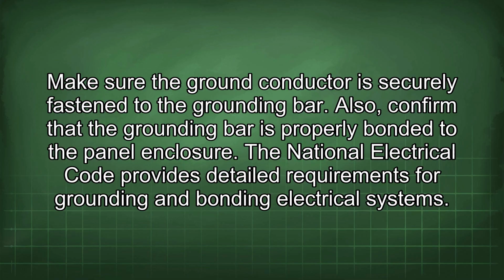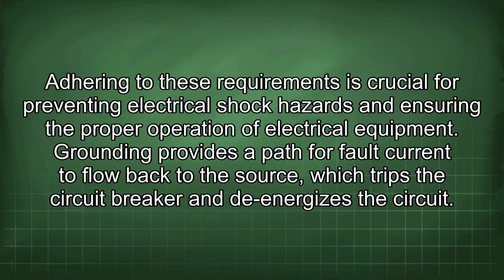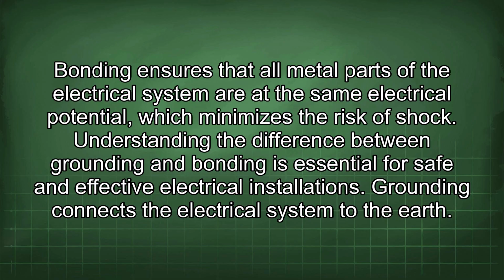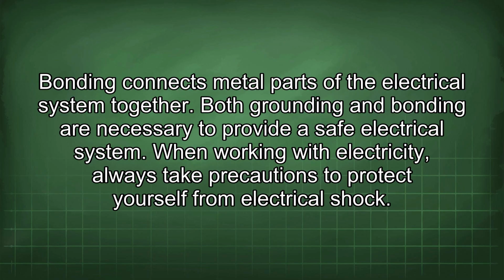The National Electrical Code provides detailed requirements for grounding and bonding electrical systems. Adhering to these requirements is crucial for preventing electrical shock hazards and ensuring the proper operation of electrical equipment. Grounding provides a path for fault current to flow back to the source, which trips the circuit breaker and de-energizes the circuit. Bonding ensures that all metal parts of the electrical system are at the same electrical potential, which minimizes the risk of shock. Understanding the difference between grounding and bonding is essential for safe and effective electrical installations. Grounding connects the electrical system to the earth. Bonding connects metal parts of the electrical system together. Both grounding and bonding are necessary to provide a safe electrical system.